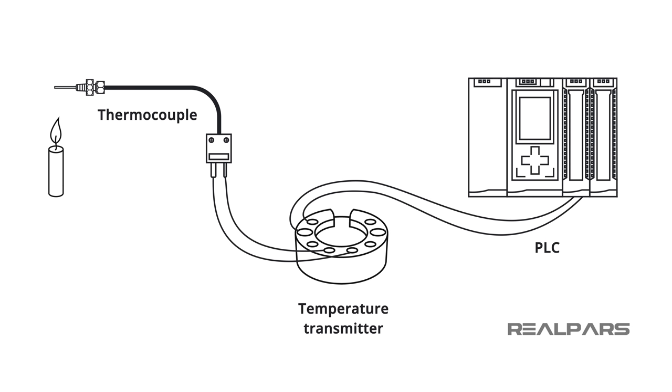Here's an example. We've already talked about a thermocouple and the voltage output created when it is heated. Unfortunately, the voltage output of a thermocouple is miniscule. In our example, the thermocouple will produce a voltage output from 8 millivolts to 18 millivolts over a 450 degree Fahrenheit change in temperature.